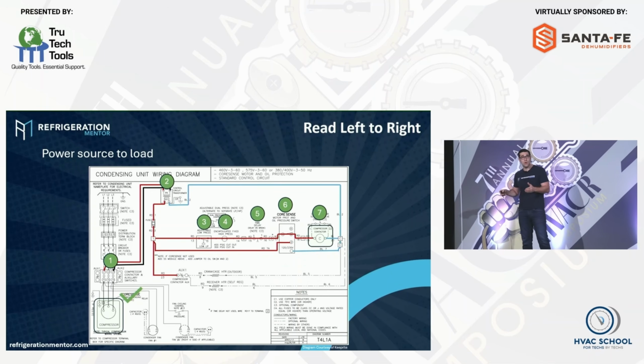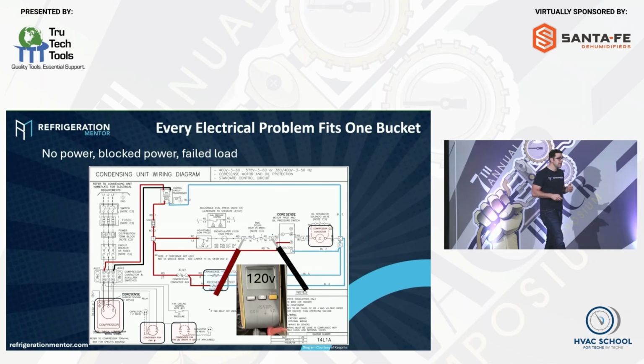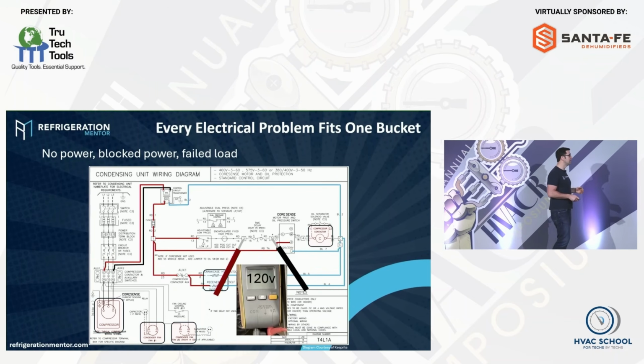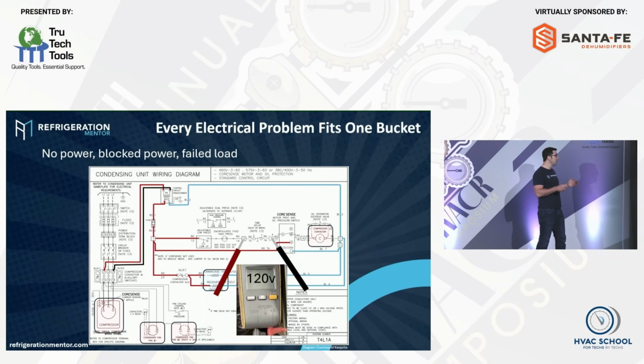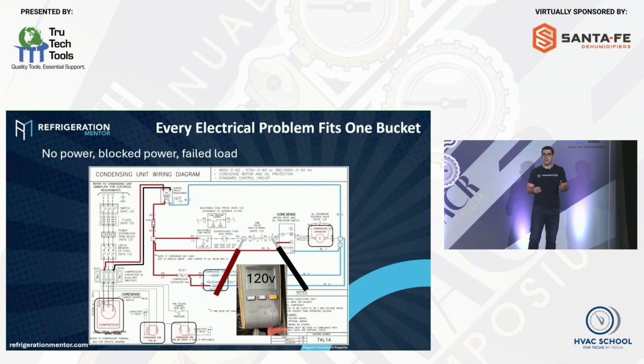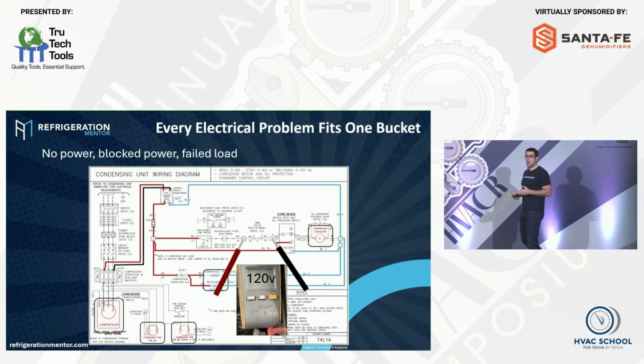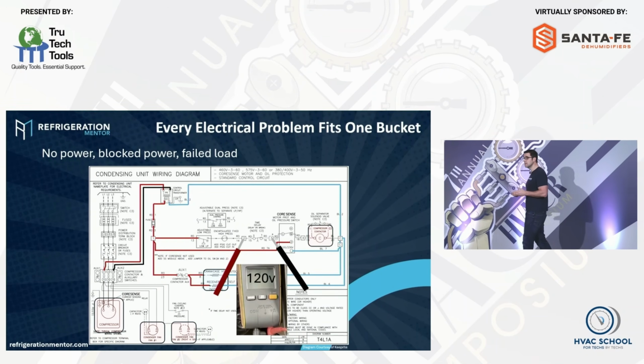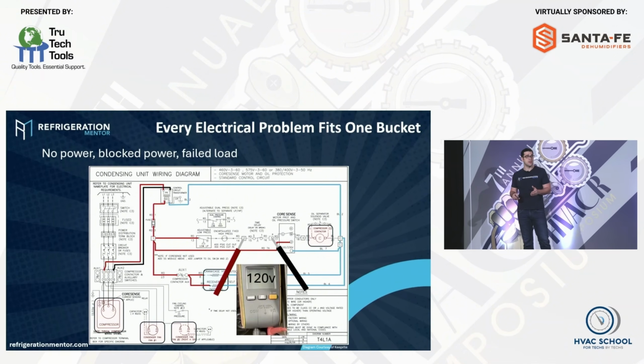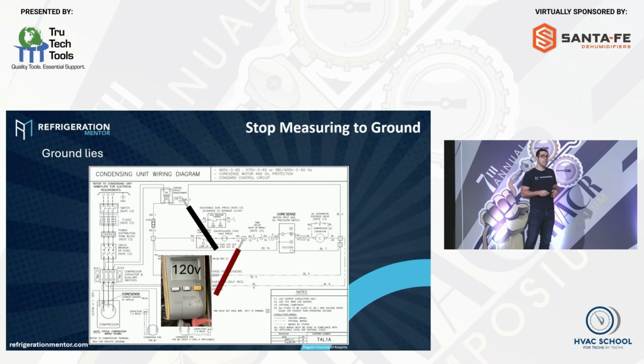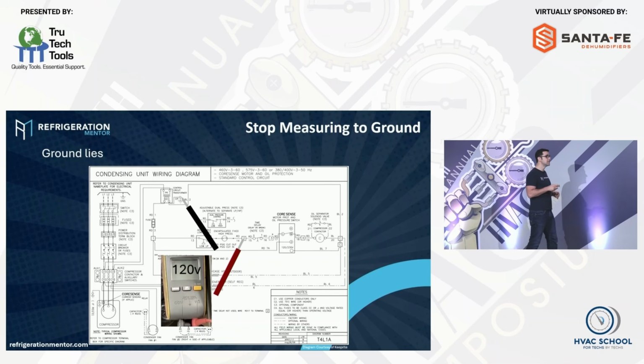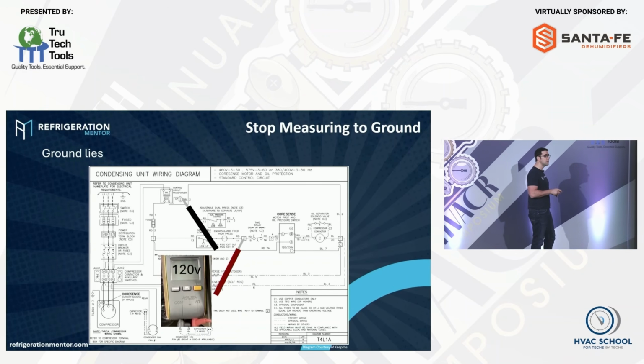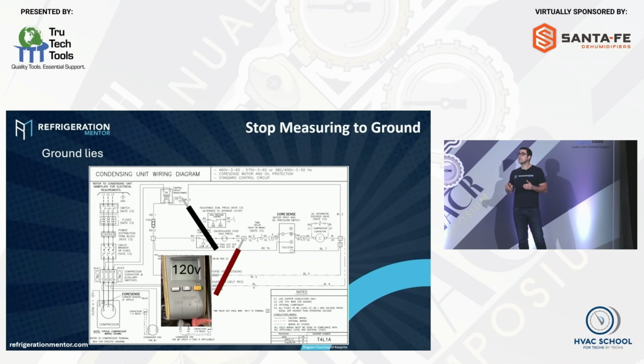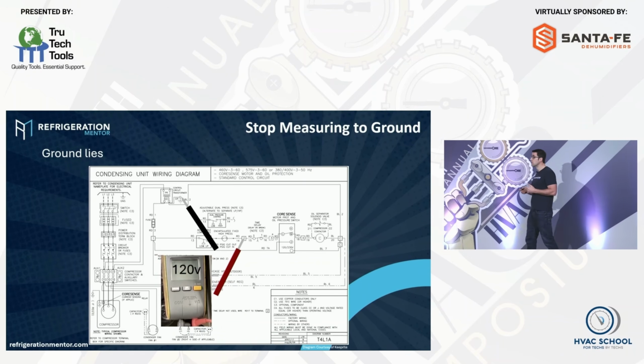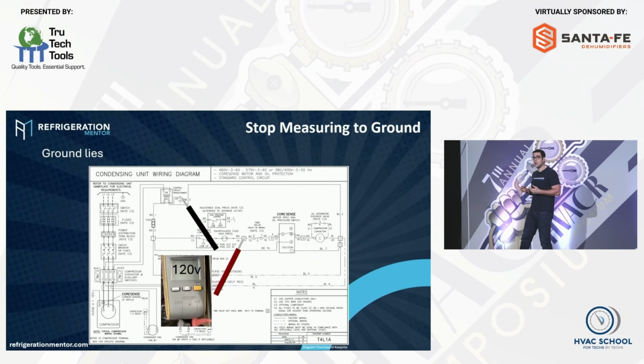It is so important. Every electrical problem fits in one bucket. No power, blocked power, or failed load. That's it. No power, blocked power, or failed load. When we understand this, this is going to really help fast track your troubleshooting. Stop measuring to ground. Stop measuring to ground. This is what tricked me up for years, what took me a lot longer to be a really good technician and really troubleshoot a lot quicker.